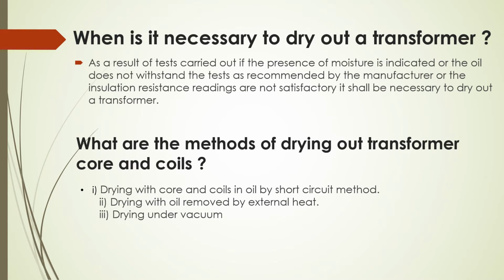So friends, let us see the typical questions asked during an electrical engineer's job interview. When is it necessary to dry out a transformer? As a result of tests carried out, if the presence of moisture is indicated, or the oil does not withstand the test as recommended by the manufacturer, or the insulation resistance readings are not satisfactory, it shall be necessary to dry out the transformer.